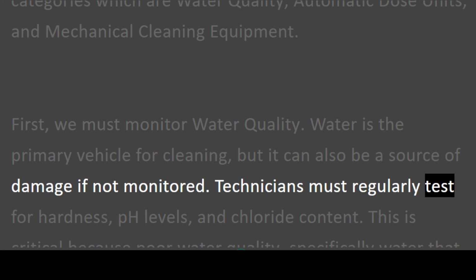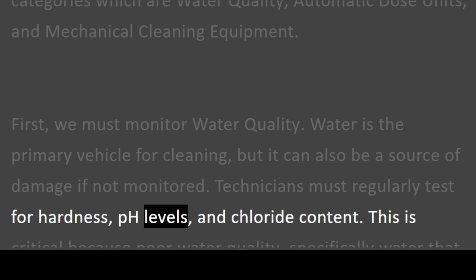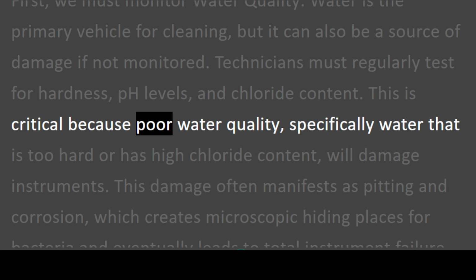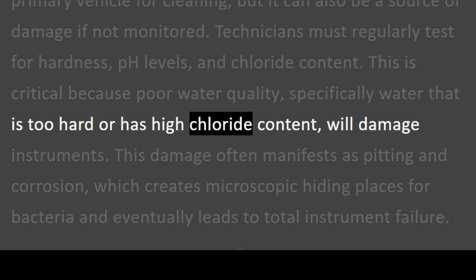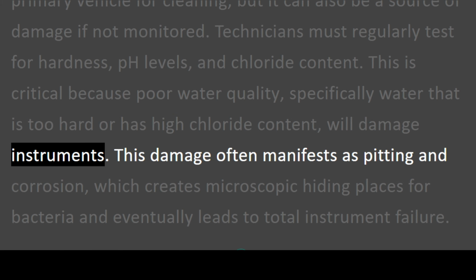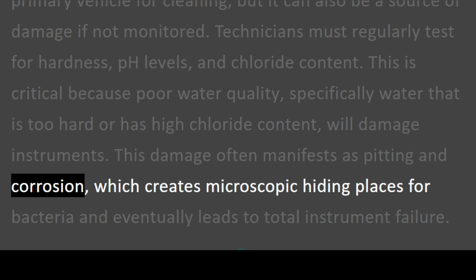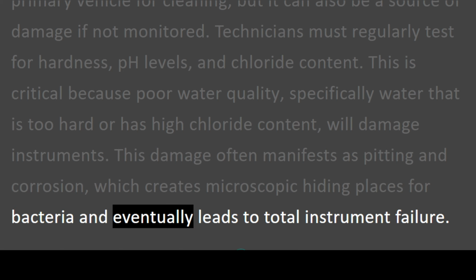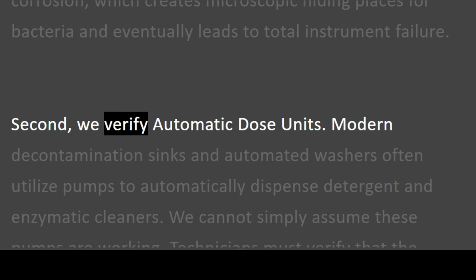Technicians must regularly test for hardness, pH levels, and chloride content. This is critical because poor water quality, specifically water that is too hard or has high chloride content, will damage instruments. This damage often manifests as pitting and corrosion, which creates microscopic hiding places for bacteria and eventually leads to total instrument failure. Second, we verify Automatic Dose Units.